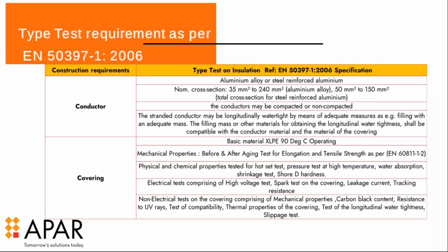So if I can talk about the type testing requirements as per the EN 50397 part 1, it also talks about the construction requirements of the conductor, that is the aluminum or the steel reinforced, like AAAC or ACSR or AL59 or whatever you want to use. Conductors of high ampacity can also be used in this covered conductor technology. The normal cross-sectional areas are 35 square mm to 240 square mm, and the conductor can be compacted or non-compacted, both kinds can be used.